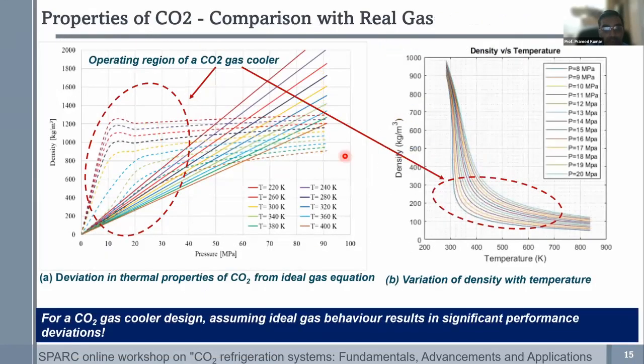And again, what it means also in terms of heat transfer, when you're developing gas coolers, particularly gas coolers operating in the transcritical region, or also undergoing subcritical operation, you have to ensure that you adequately capture the property variations of carbon dioxide in the region of operation, where there is a large density variation. See, these are all the ideal gas behavior, and this is superposed with carbon dioxide properties. So you see how much of a deviation there is from the ideal gas behavior. In this region, where most of our operations in transcritical refrigeration take place, you have to ensure that these points of inflection are adequately accounted for in your heat exchanger design.